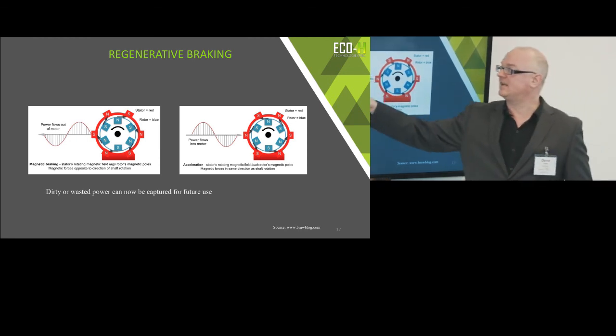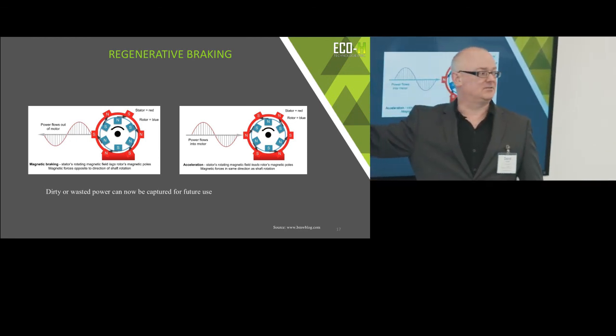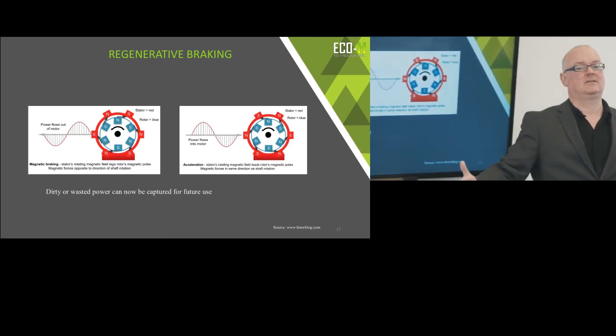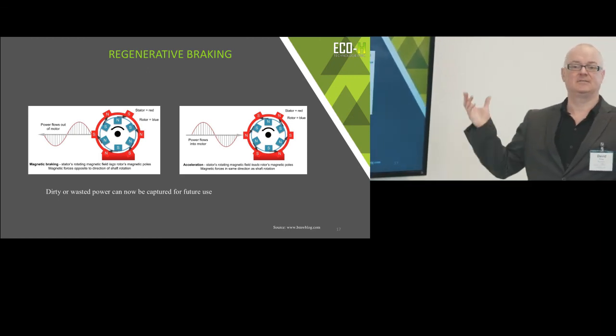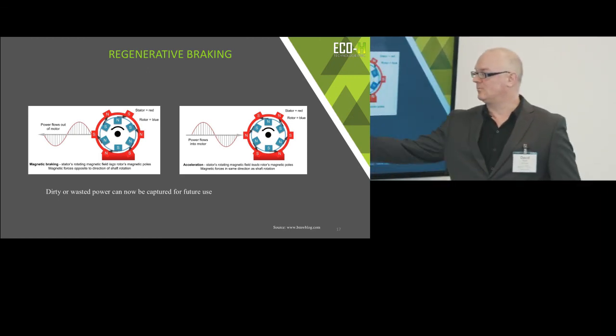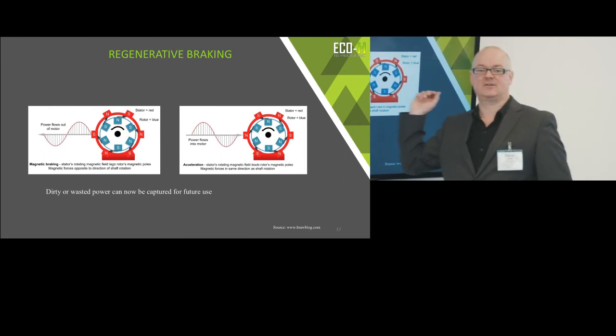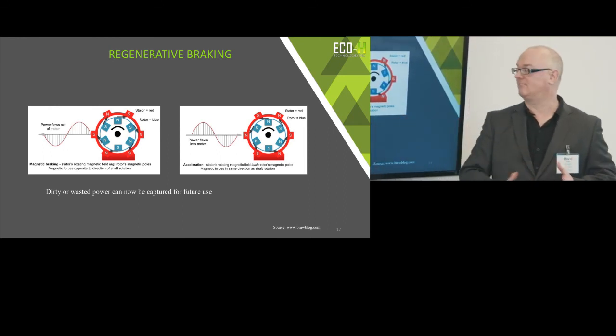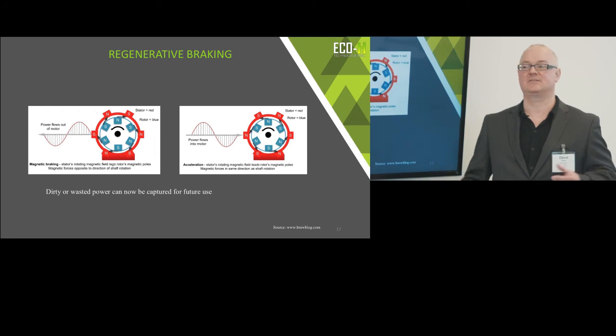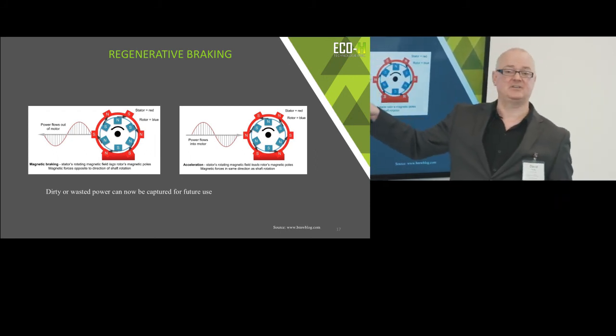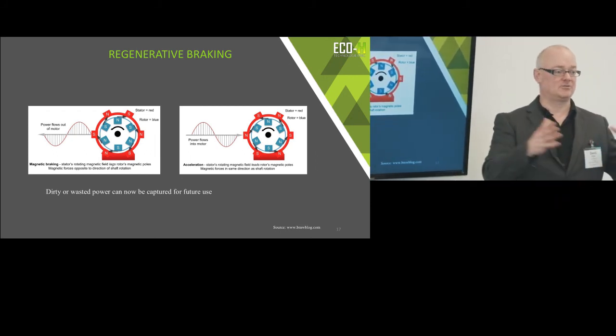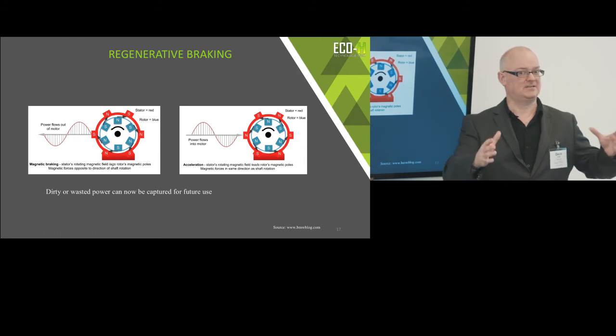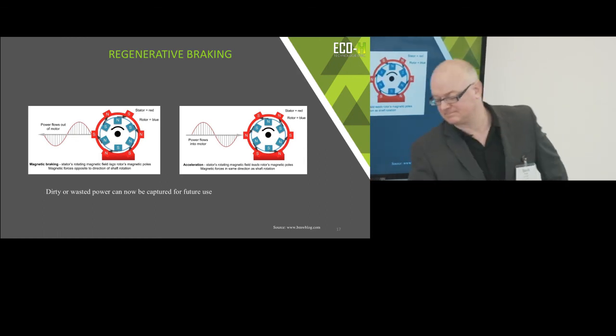So regenerative braking is now diverted to load banks or heaters, and you're burning off all this excess energy. So why can't you use it? Well, you can't use it because you can't throw it back in, there's nowhere to store it. But with an energy storage system or a battery system, any of this regenerative energy can be used, and again, it all tops up your energy reservoir for later, whenever you need it.